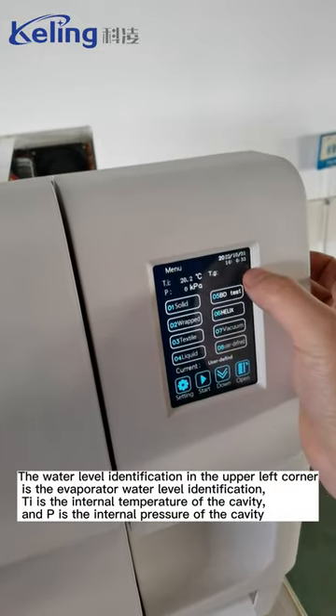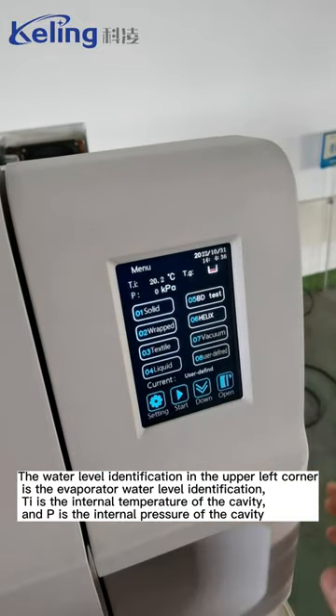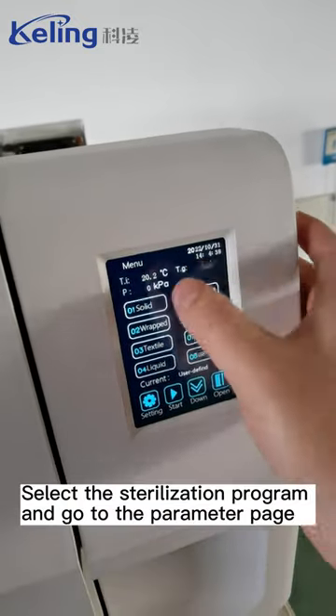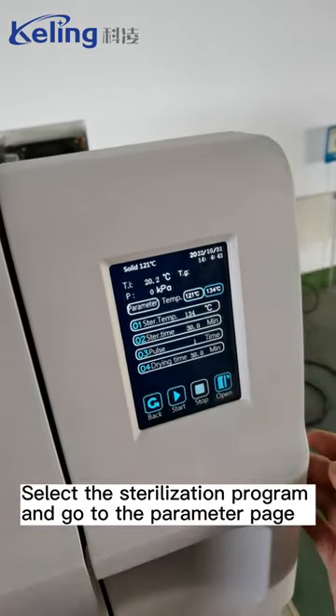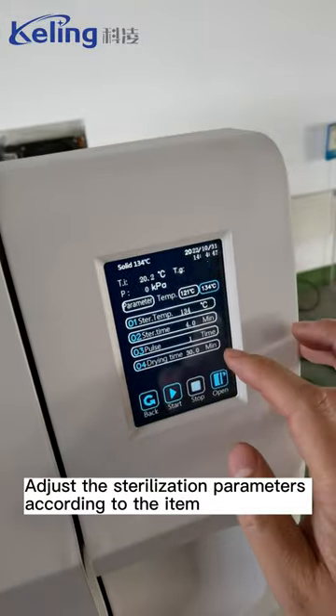The water level identification in the upper left corner is the evaporator water level identification. TI is the internal temperature of the cavity, and P is the internal pressure of the cavity. Select the sterilization program and go to the parameter page. Adjust the sterilization parameters according to the item.